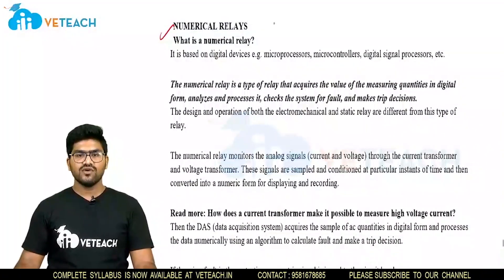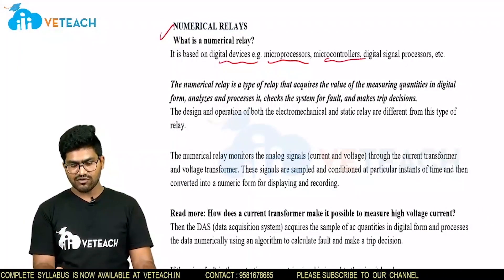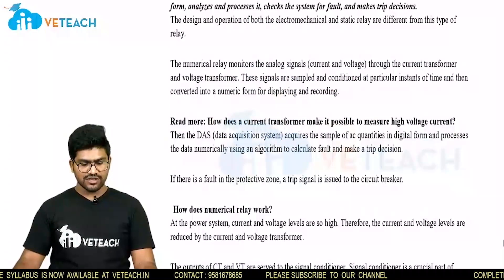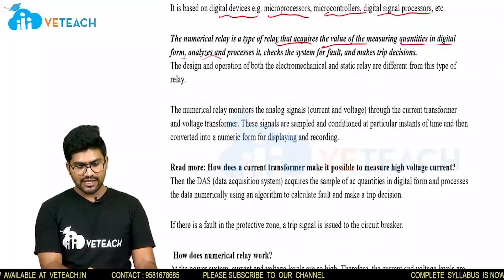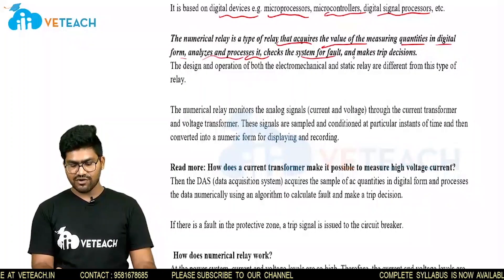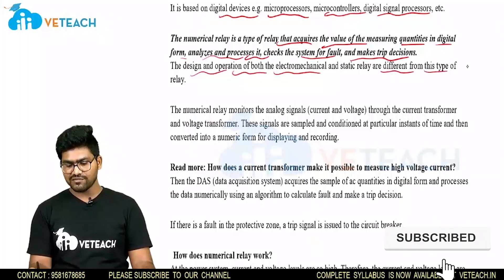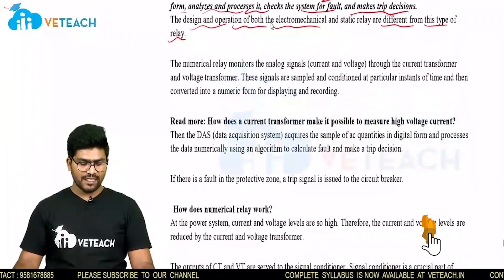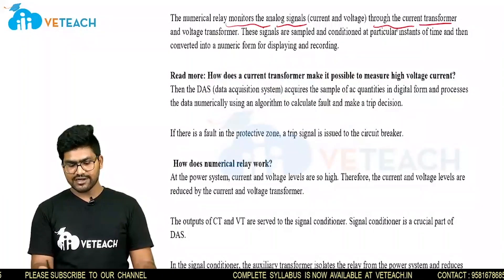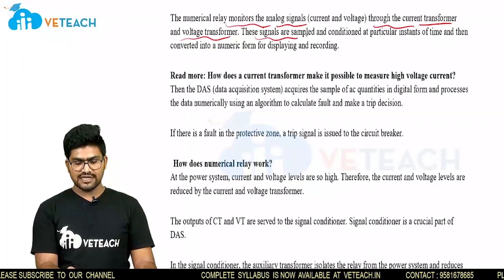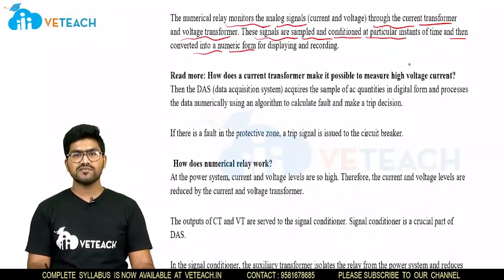Coming to numerical relays — what is a numerical relay? It is based on digital devices such as microprocessors, microcontrollers, digital signal processors, etc. The numerical relay is a type of relay that acquires the value of measuring quantities in digital form, analyzes and processes it, checks the system for fault, and makes trip decisions. The design and operation of both electromechanical and static relays are different from this type of relay. The numerical relay monitors analog signals — current and voltage — through a current transformer and voltage transformer. These signals are sampled and conditioned at a particular instance of time and then converted into a numeric form for displaying and recording.